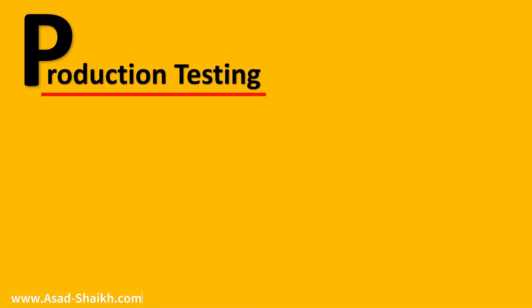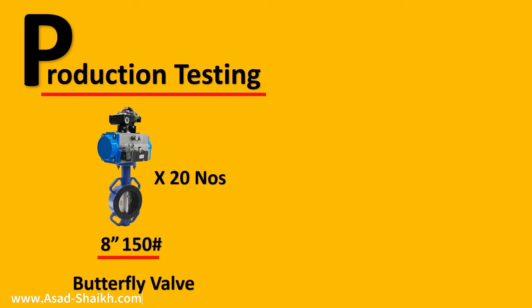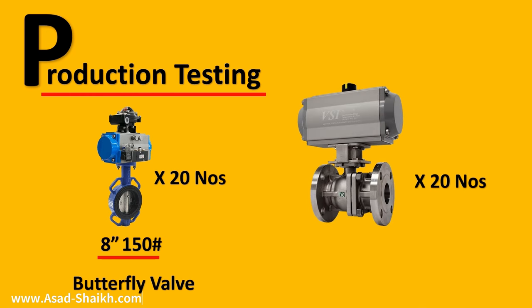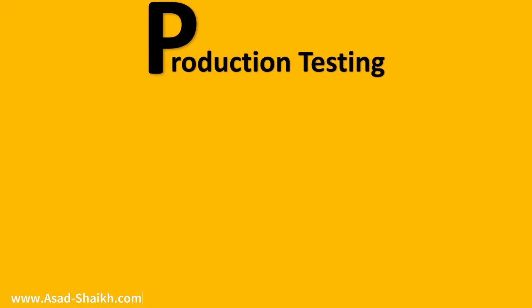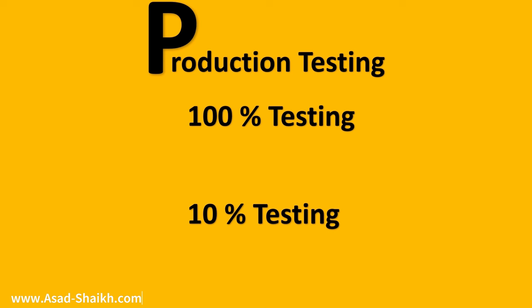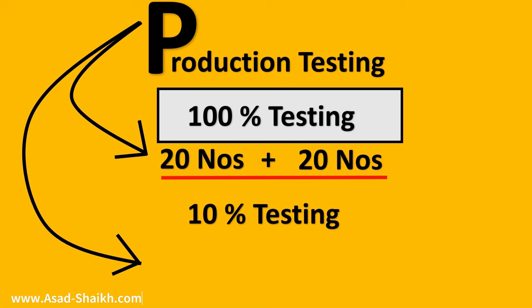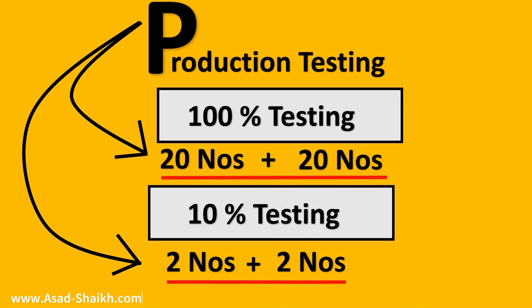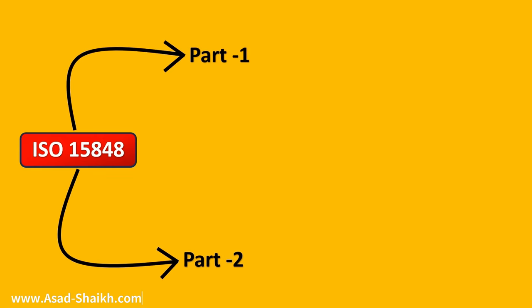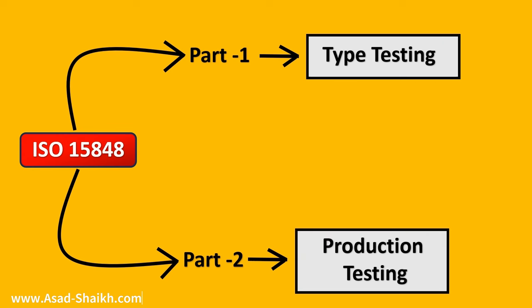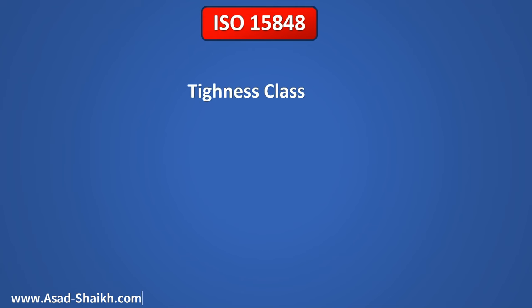The opposite of type testing is production testing. Imagine you have 20 butterfly valves — say 8-inch 150 rating — and 20 ball valves, all 2-inch 600 rating. For production testing, you first decide whether it will be 100% testing or only 10% testing. If 100%, all 20 of both valve types must be tested. If only 10%, then just 2 valves of each type are selected, but they must be chosen at random. ISO 15848 is divided into Part 1, which deals with type testing, and Part 2, which deals with production testing.